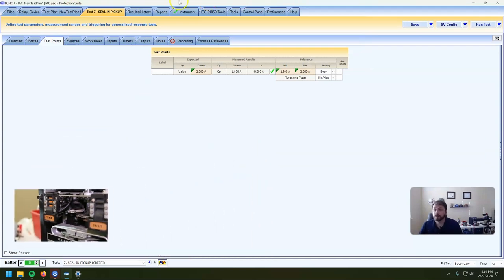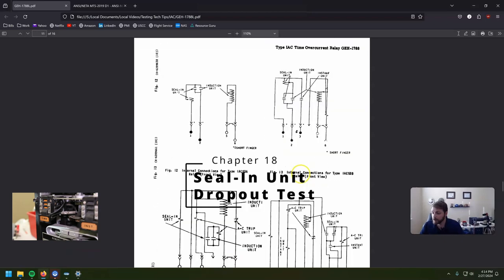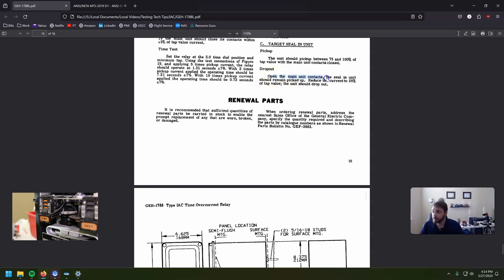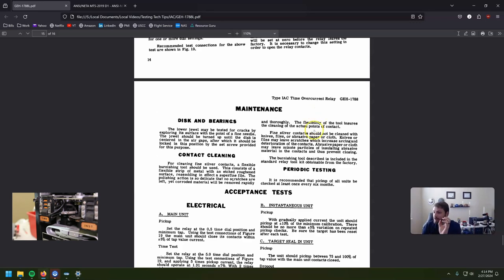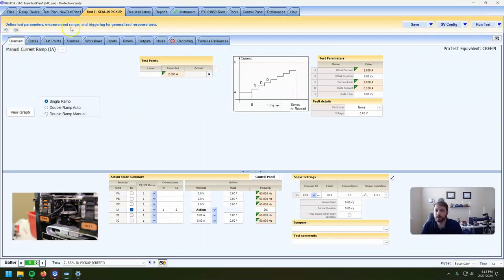The next and last test for the GE IAC relay is the seal-in dropout. We've held the disc closed, the seal-in has picked up and is closed. Then we open the main contact and ramp that DC current down until the seal-in contact opens up. And that needs to happen before 25% — they do give us a tolerance on that one.